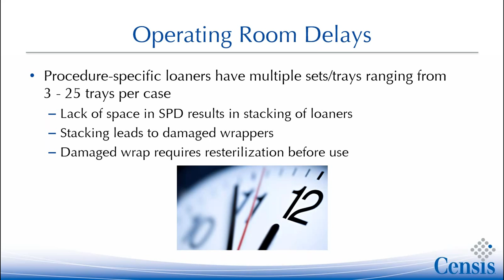If loaners are wrapped in disposable wrap, what usually happens is we drag those trays across each other and we put holes in those wrappers. Those wrappers that become damaged must be reprocessed. And where do we start the reprocessing? In decontam. You cannot take those trays, just unwrap them in assembly, and then just put new wrap on them. They need to go through the entire sterilization process.